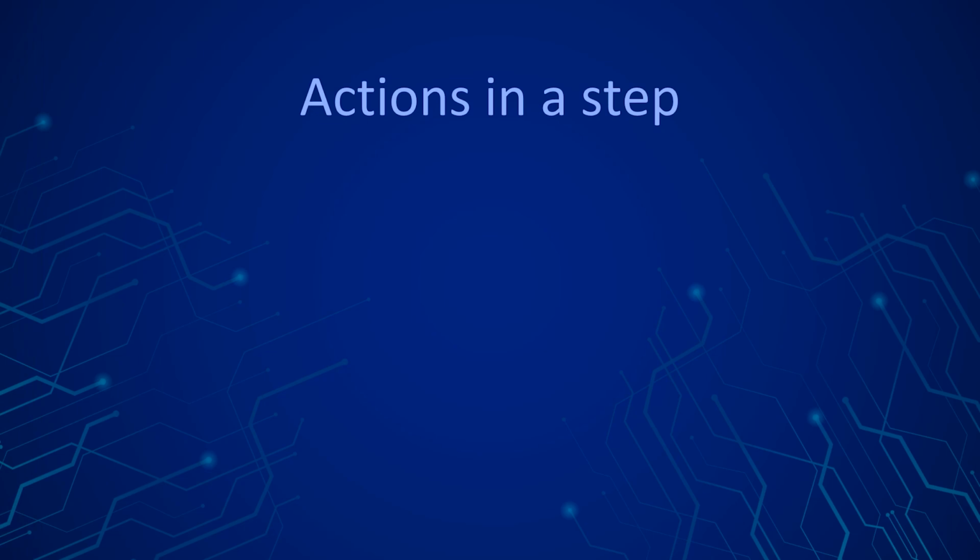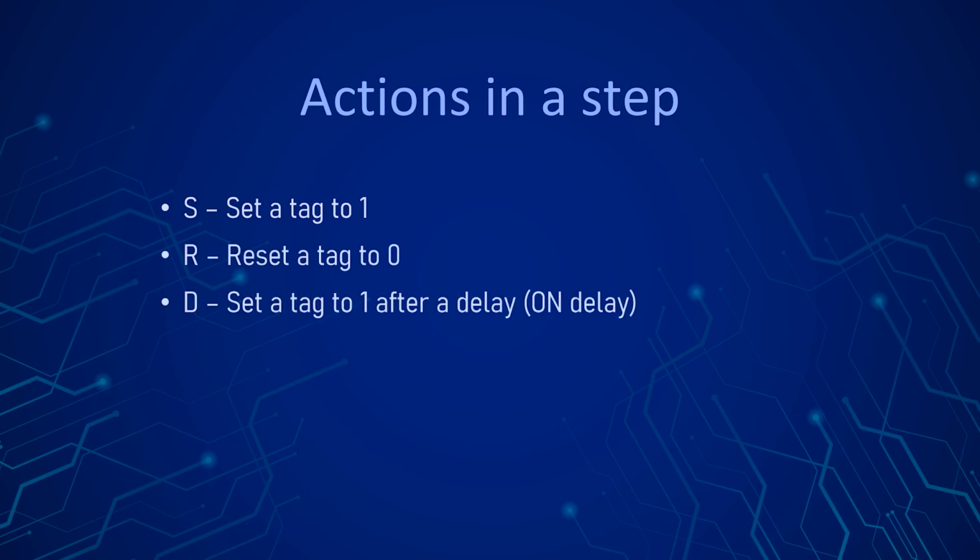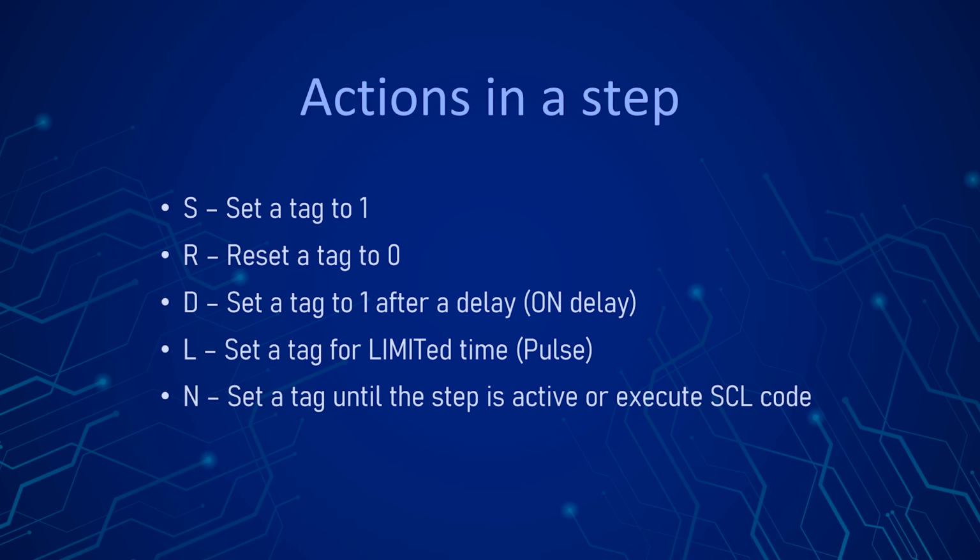In each step you can have the following actions. S: set a tag to 1. R: set a tag to 0. D: set a tag to 1, after a specified time. L: set a tag to 1, for a specific period. N: set a tag to 1 as long as the step is active, or give value to a variable in SCL.